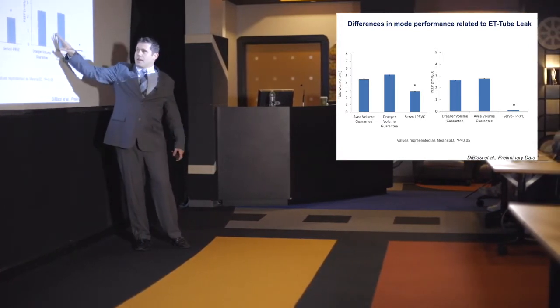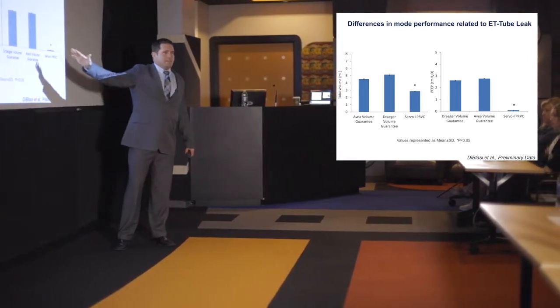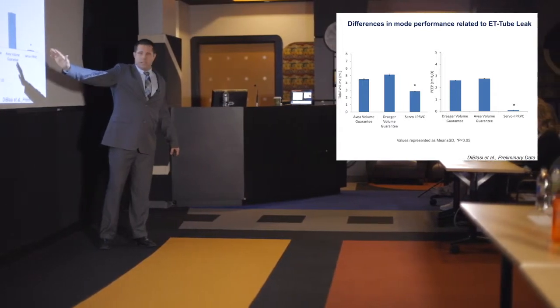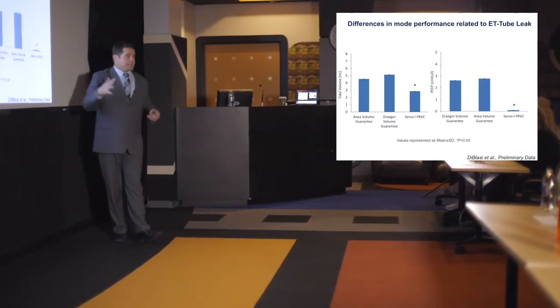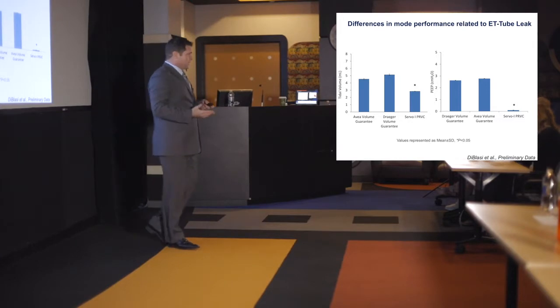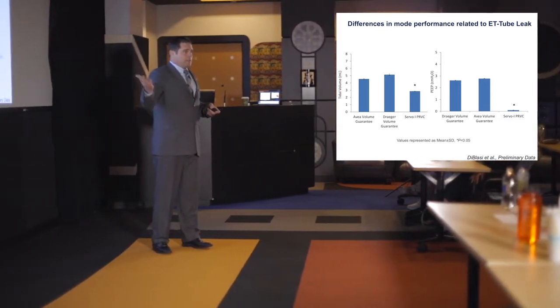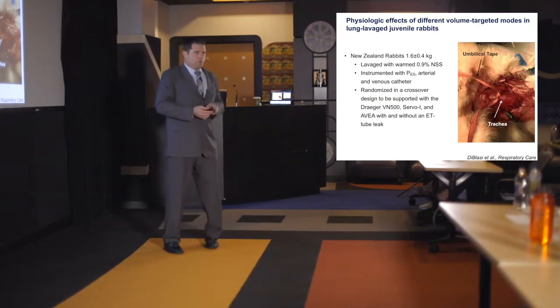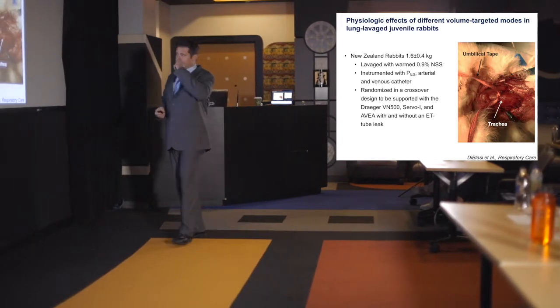But when it comes to PEEP, none of the ventilators really do an excellent job. Again, this is a static lung model. It's got a fixed leak. The Servo I, because it doesn't have a leak compensation algorithm on exhalation, is not able to provide the PEEP, at least with the I. But I think with the new N and U, it's really changed a lot.